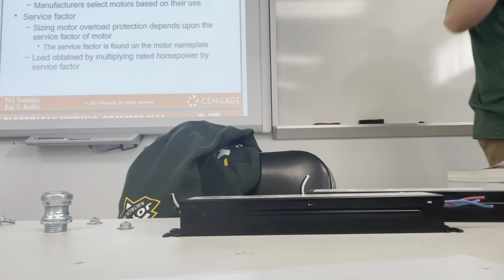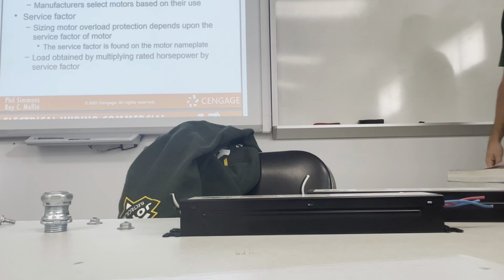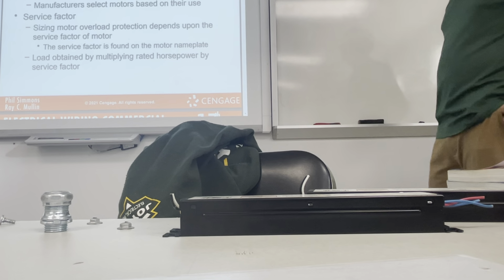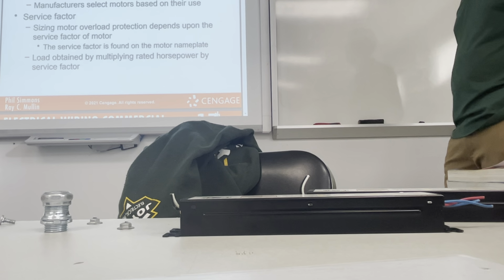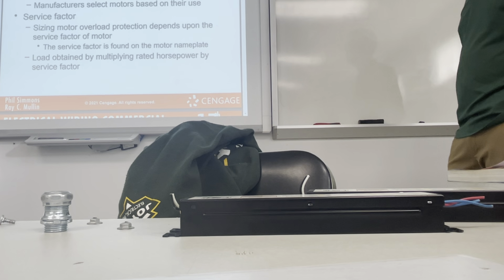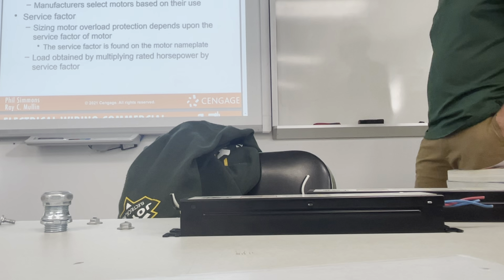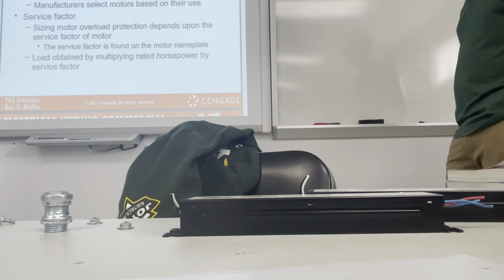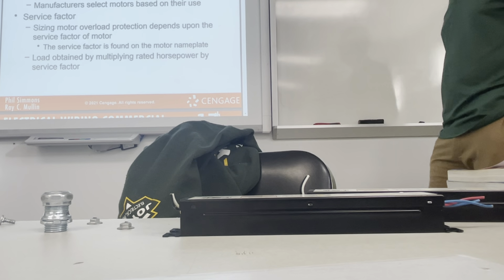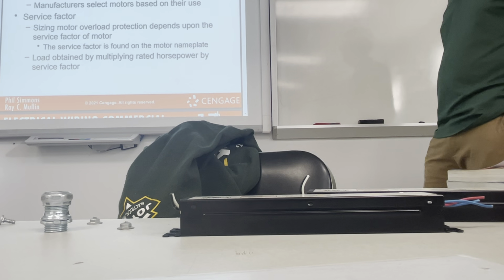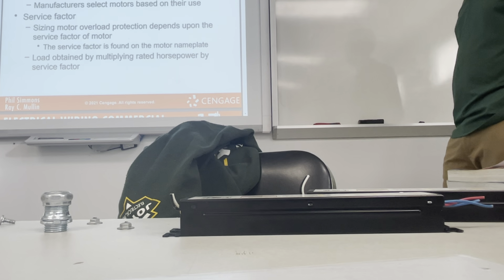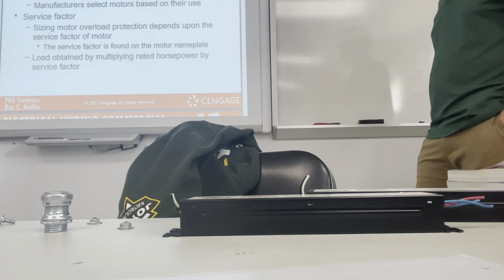Who's that? Start that from? Basics of insulation. Motors have different classes of insulation. Manufacturers select motors based on their use. Service factor. Sizing motor overload protection depends upon the service factor of motor. The service factor is found on the motor nameplate. Load obtained by multiplying rated horsepower by service factor.